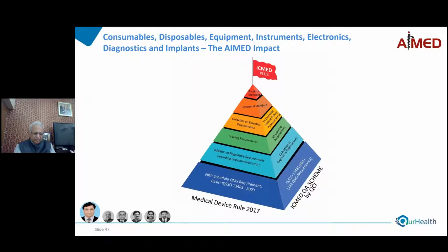Over here you'll find we benchmarked the ICMED scheme and the medical device rules which followed later on. We used the experience of the ICMED scheme and made sure that the rules and regulations which came for medical devices were robust and incorporated all the same elements. So the base of the pyramid is a quality management system standard. On that we've added the 23 regulatory requirements I told you about. Then we've added the 16 labeling requirements. Then we've interspaced that with the horizontal standards, which are based on risk management, essential principles of safety, sterilization validation, process validation, and such things which are required in manufacturing. And on top of that, last comes the product standard, which is only available in certain cases.